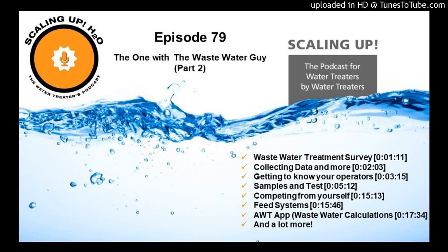I had one problem where somebody did not clean out a tank properly, and we brought an organic chemical in on top of an inorganic, and it turned into gel. And we had a mess. And needless to say, we didn't get that business. But I won't take responsibility for that one. Bottom line is you've got to clean the equipment out. So really understand, clean the lines out, flush the lines out. That's key to making sure your trial is successful, making sure you cover every little part of what can happen. Again, the equipment is always a big issue.